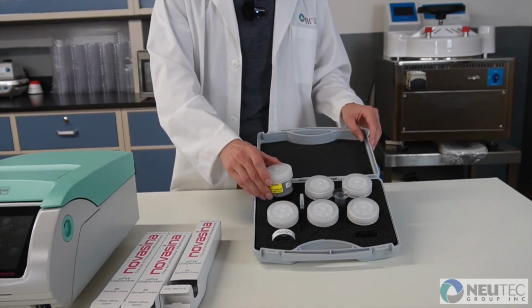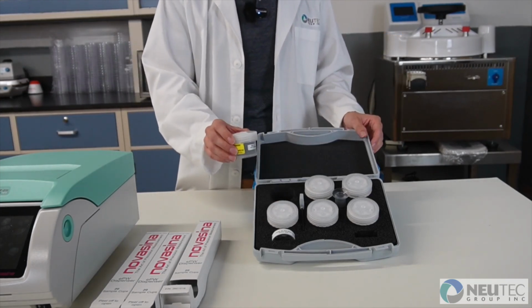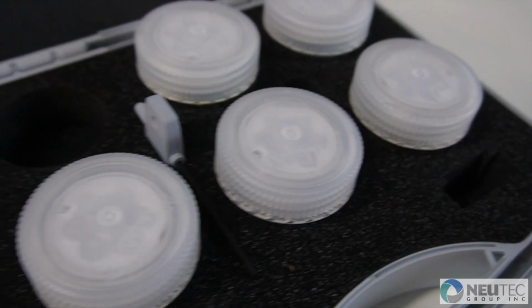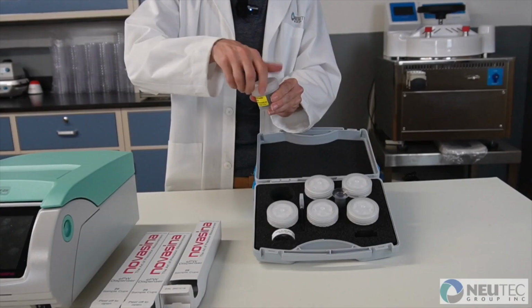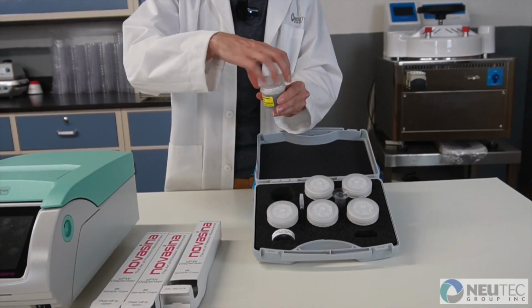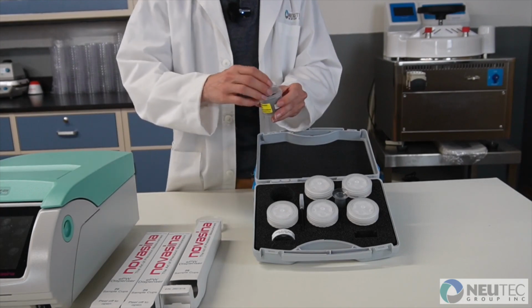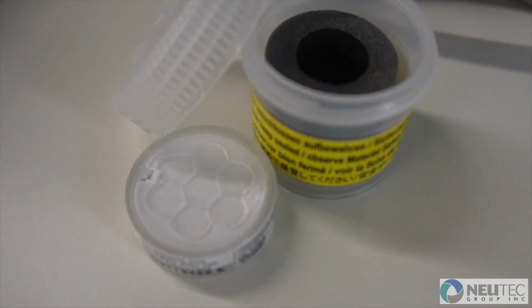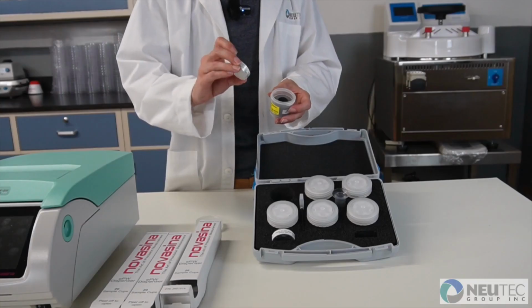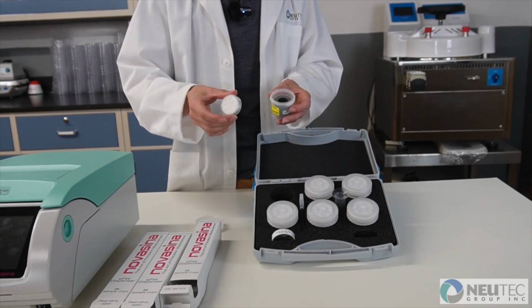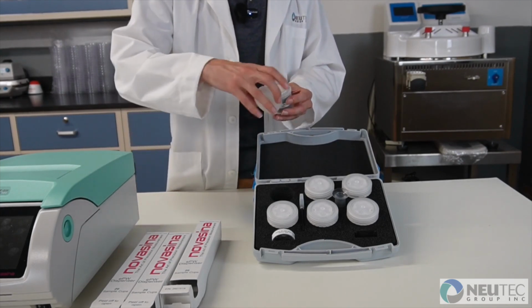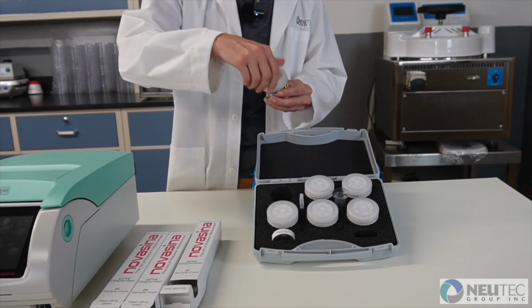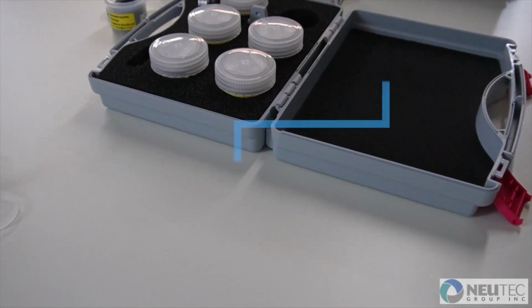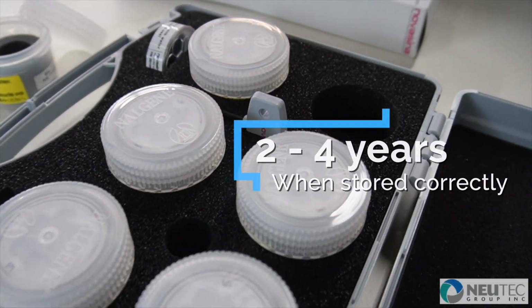The LabMaster Neo comes with 6 individual salt calibration standards. Each one of these standards that reads at a set humidity comes with its own cup. Keep these cups. The salts should be resealed after each use so that you'll get the maximum lifetime out of them. They should last you between 2 and 4 years if stored correctly.